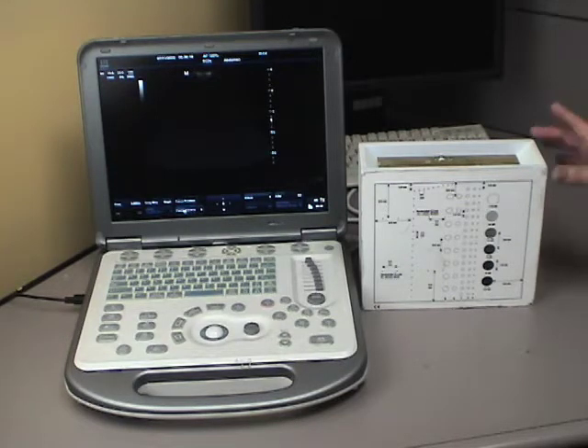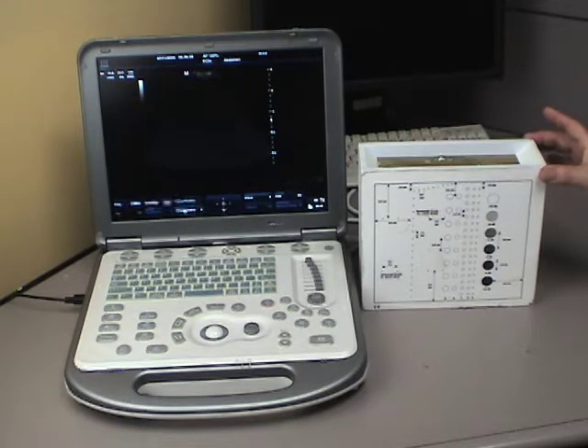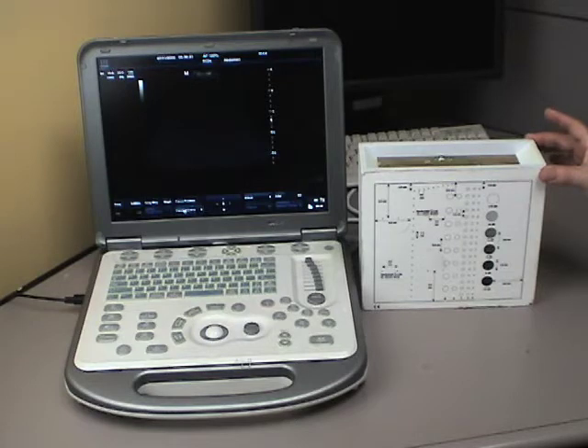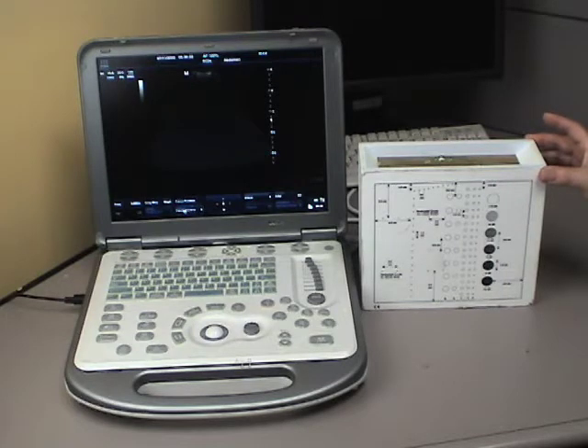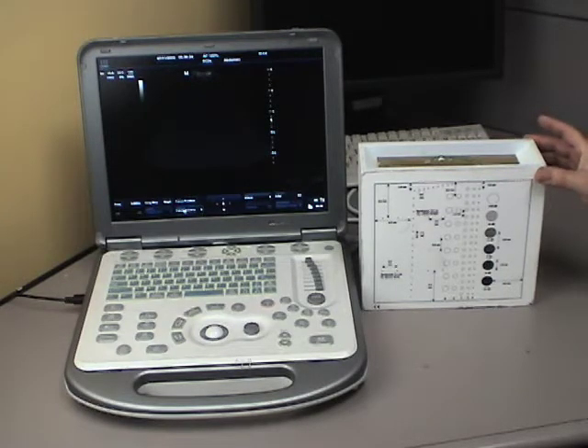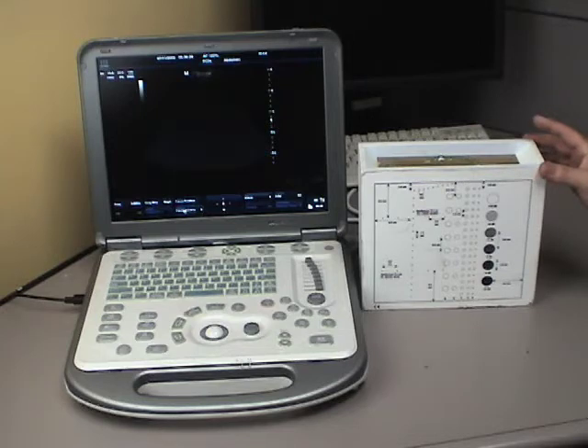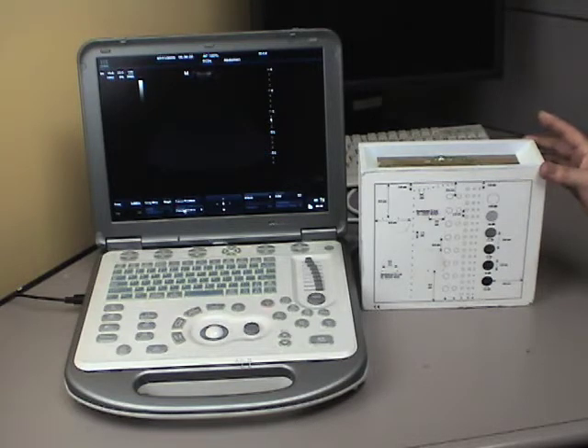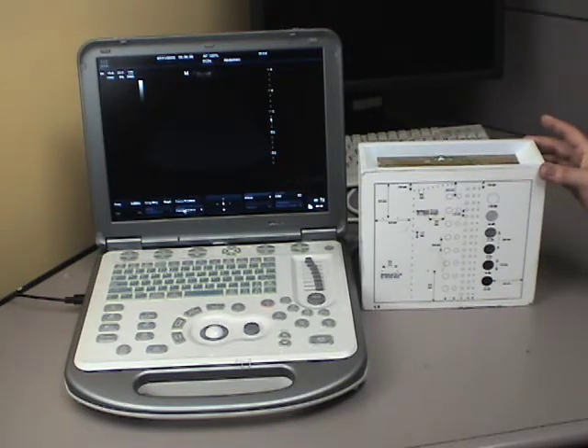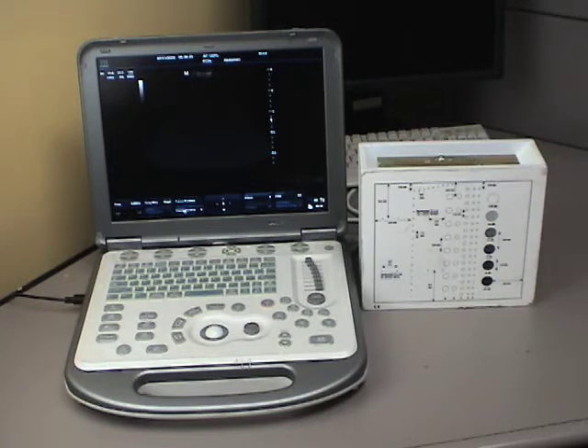This is one of the most basic phantoms that you'll find. There's a wide variety of phantoms used for ultrasound, and in general a phantom just means it's something that's taken place of a body that you can image. The real advantages of that is it gives you something that's consistent and stable that you're looking at the same thing each time.